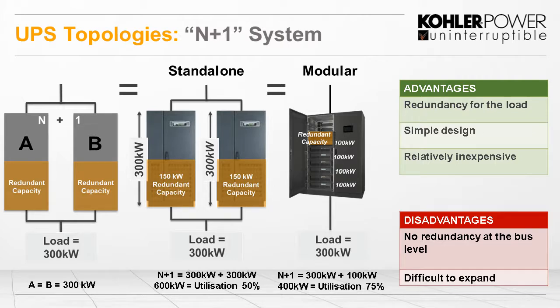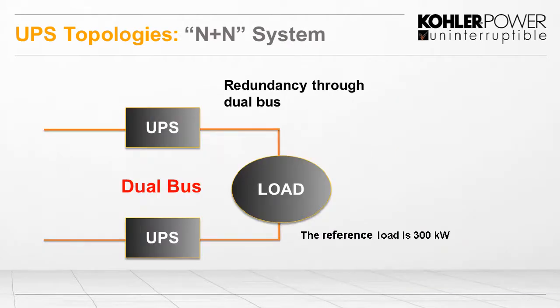Now, modern load has been developed with dual supplies. So many servers, many computer equipment manufacturers are building all their equipment with two supplies in there. And this is designed to be fed from two different sources. So if a power supply or the supply coming in is lost on one side, typically an A and a B, we can still run from the other side.